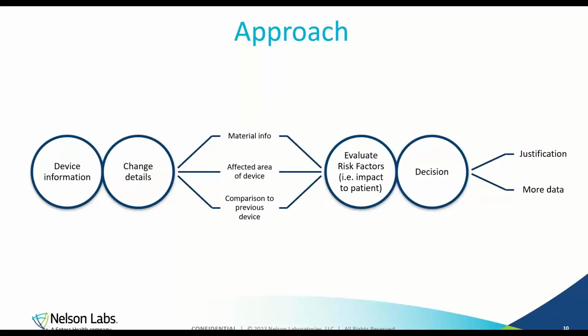And then our approach. So this is just to give you an outline of how I will walk through a biological risk assessment. My very first point of focus is going to be on device information. I would say for our team, this is the area that is usually the weakest explained to us from any manufacturer that comes to us, because there's so much concern about the back end. Are we going to have to do more testing? How many devices do I have to make? And there's a lot of concern and drive to get to that end point.